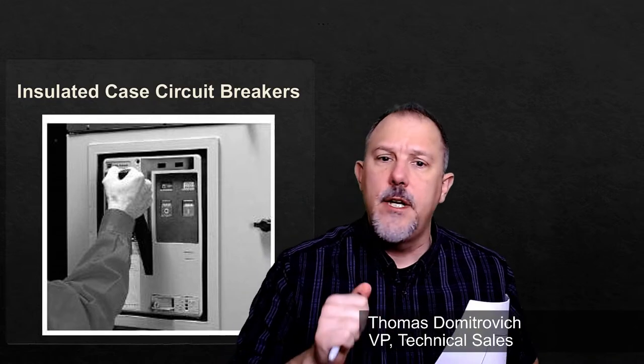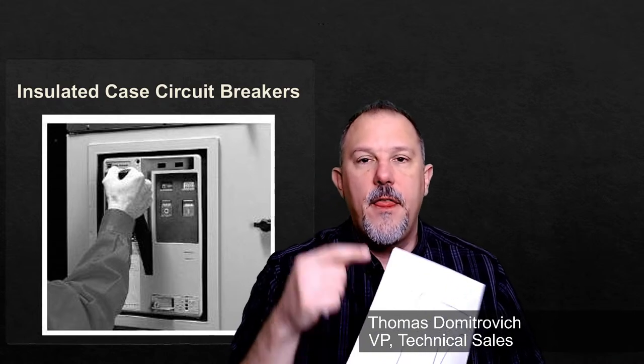But Robert, you also, if you think about, you have a panel board, you have a switchboard, and then you have switchgear. I can put panel boards in a switchboard. I can put molded case circuit breakers in a switchboard and an insulated case circuit breaker in a switchboard. I can't put a power circuit breaker in a switchboard. Power circuit breakers go into low voltage assemblies based on listing, etc.